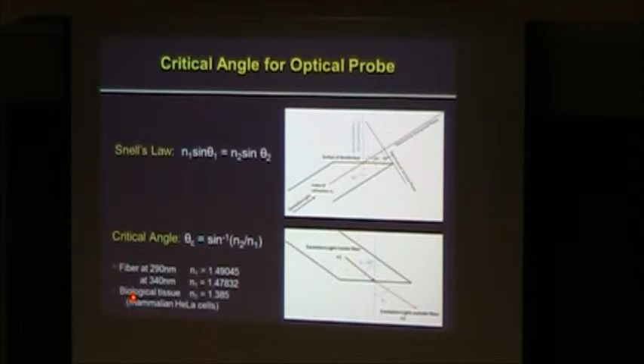So now we are getting into areas that you are very familiar with. We look at the critical angle. We calculated it using Snell's law, and fortunately for us, we are inserting this into biological tissues, so the refractive index is closer to water, and we use those numbers. The issue, of course, is how much power we need at what angle, so you can use the Fresnel equations and figure out the numbers. Around about 60 degrees, you can keep the losses under 10%, but once you go beyond that, they increase exponentially. So after all of that haggling, right now the needle angle is set at about 60 degrees, due to all the restrictions. And the biopsy gun is a spring-loaded mechanism.